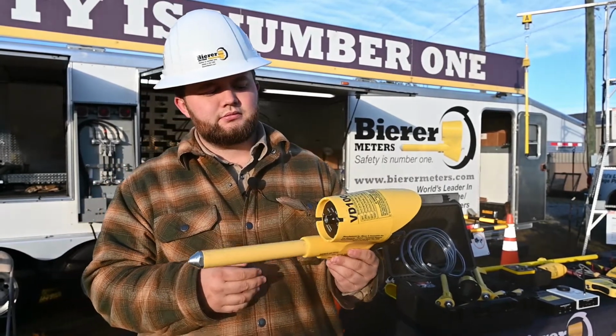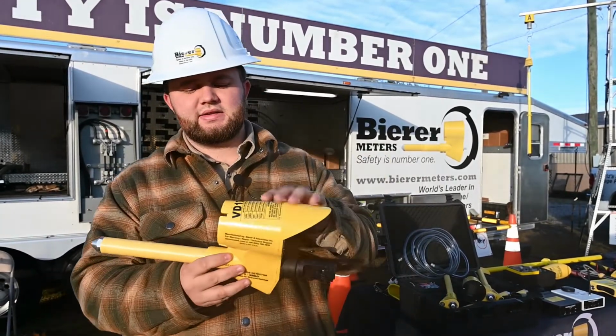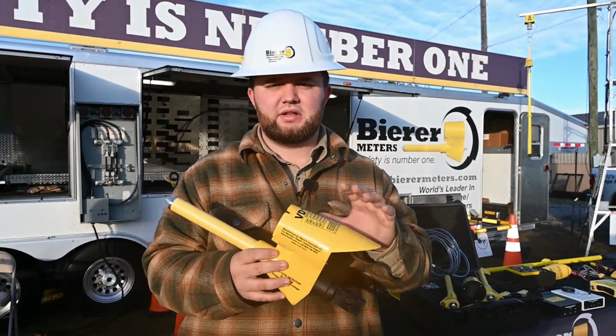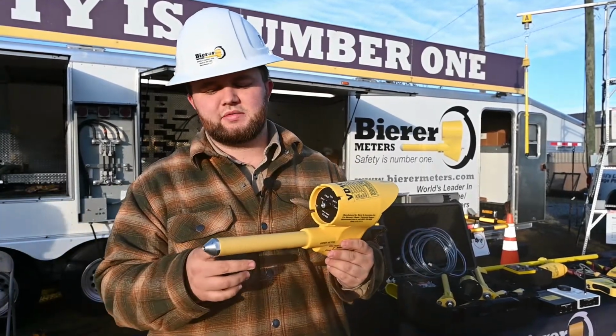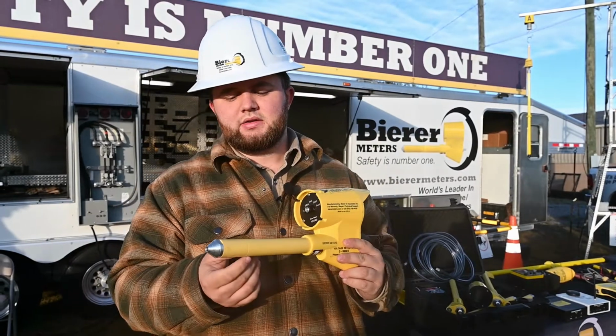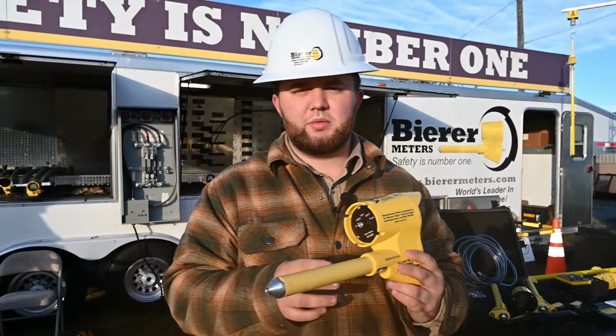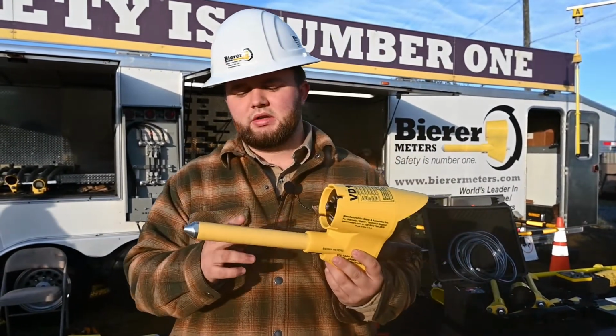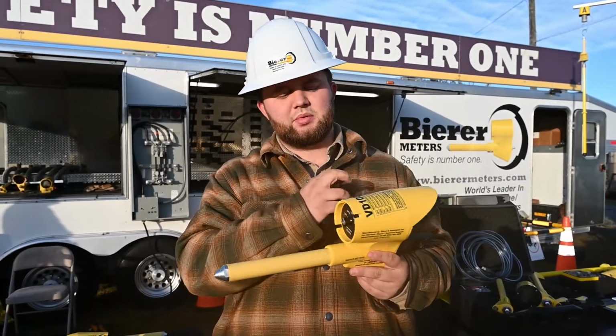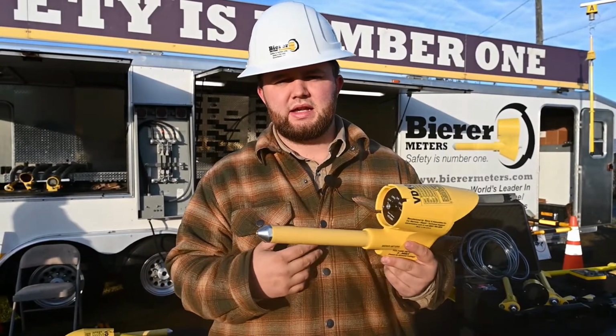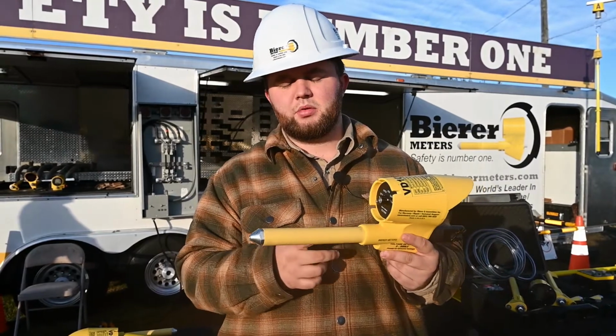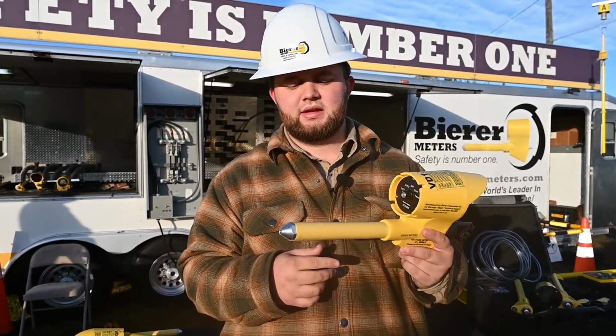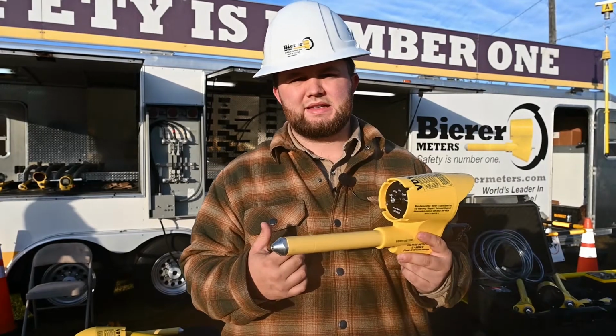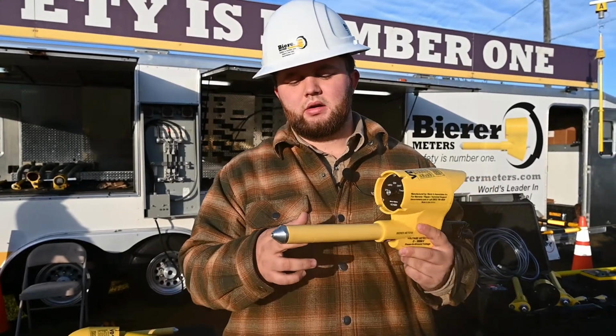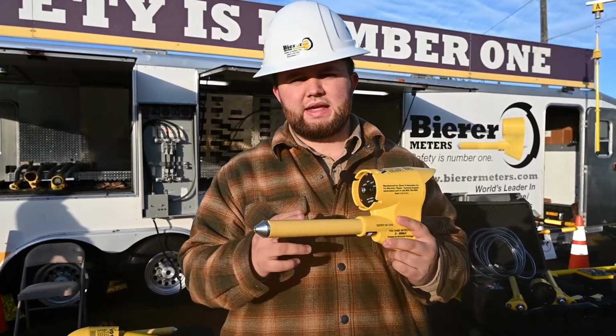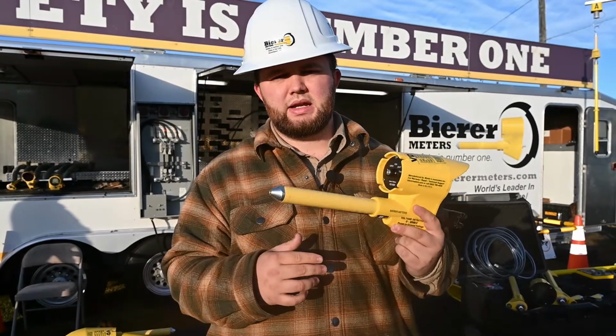So now that you've got a basic understanding, since like I said, everybody's tools have conductive components, we'll talk about some tool safety. So what we do as a manufacturer is we put resistors in the probes. Those resistors protect, again, those conductive components and you guys being the user. So we put about 25 mega ohms of resistance. Some other manufacturers only use about 6.5 mega ohms. So what we also do is we encapsulate those resistors in this probe in an epoxy.